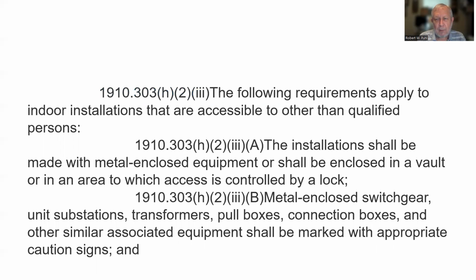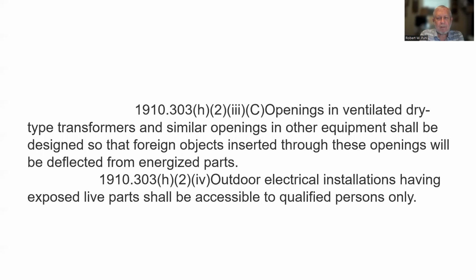And their operations. The following requirements apply to indoor installations that are accessible to other than qualified persons. The installation shall be made with metal enclosed equipment or shall be enclosed in a vault or in an area to which access is controlled by a lock. Metal enclosed switchgear, unit substations, transformers, pull boxes, connection boxes, and other similar associated equipment shall be marked with appropriate caution signs, and openings in ventilated dry type transformers and similar openings in other equipment shall be designed so that foreign objects inserted through these openings will be deflected from energized parts.